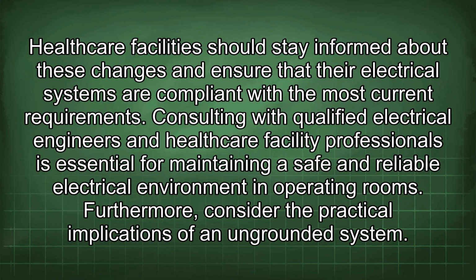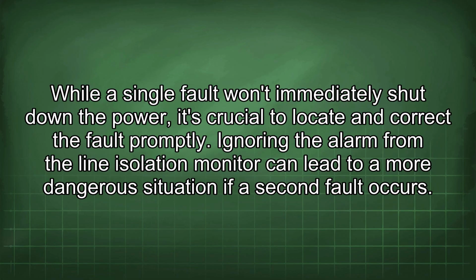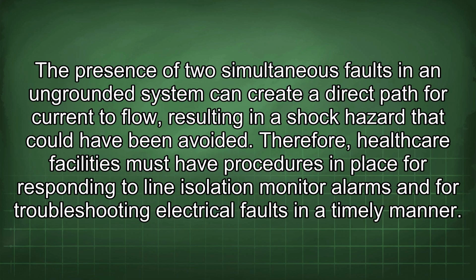in operating rooms. Furthermore, consider the practical implications of an ungrounded system. While a single fault won't immediately shut down the power, it's crucial to locate and correct the fault promptly. Ignoring the alarm from the line isolation monitor can lead to a more dangerous situation if a second fault occurs. The presence of two simultaneous faults in an ungrounded system can create a direct path for current to flow, resulting in a shock hazard that could have been avoided.